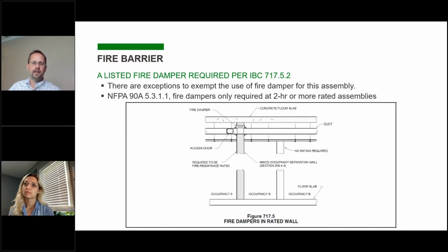But we've run across other code officials who have interpreted it in a way that if you have flex duct anywhere in the system, this exception does not apply to that system, and so they require fire dampers at every single fire barrier. It can be really confusing, and there's no way of knowing without talking to a code official. So it's important to have communication, especially on this subject, if you're working with a code official that you're not familiar with or a new jurisdiction, just to discuss how they interpret this.